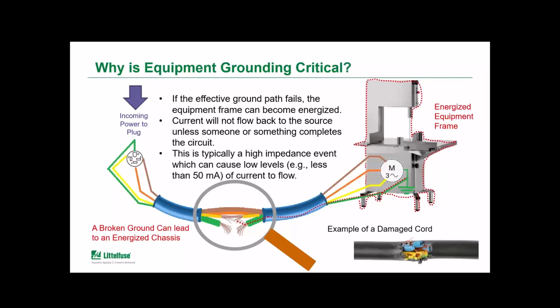So in the image on the screen, you can see the brown, orange, and yellow conductors. That's your phase A, B, C, while the green conductor would be your effective ground path, providing that path for ground fault current to flow back to the upstream source. So if the effective ground path becomes compromised, just like we're showing under that magnifying glass, the fault current may not be able to return to its source. And when there is no fault current, that means the GFCI will not trip.